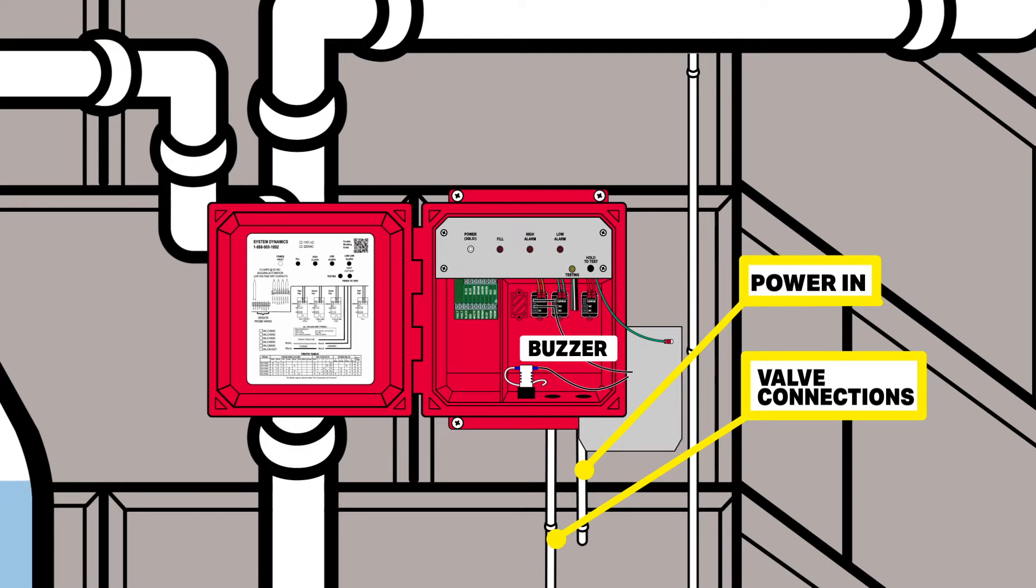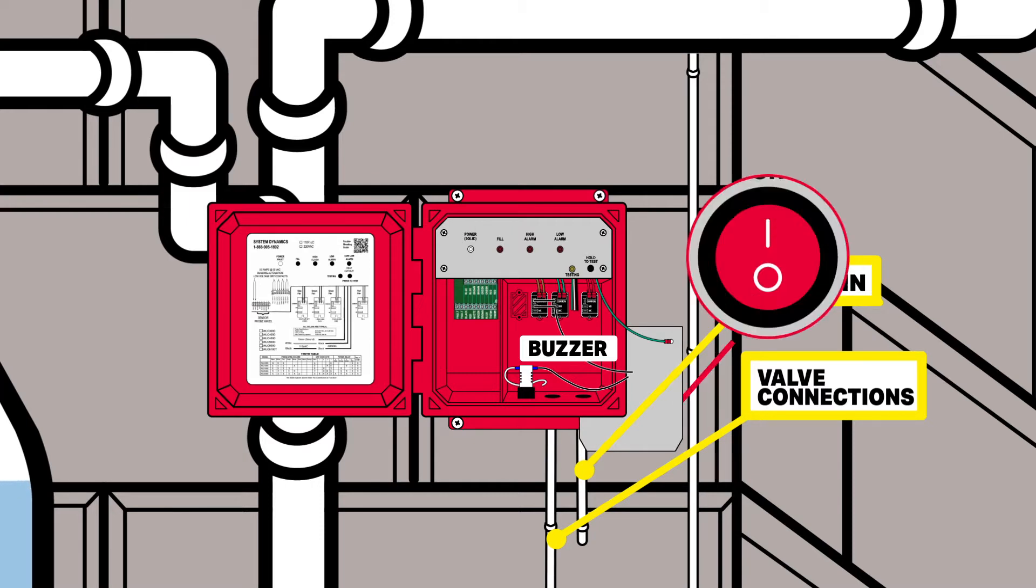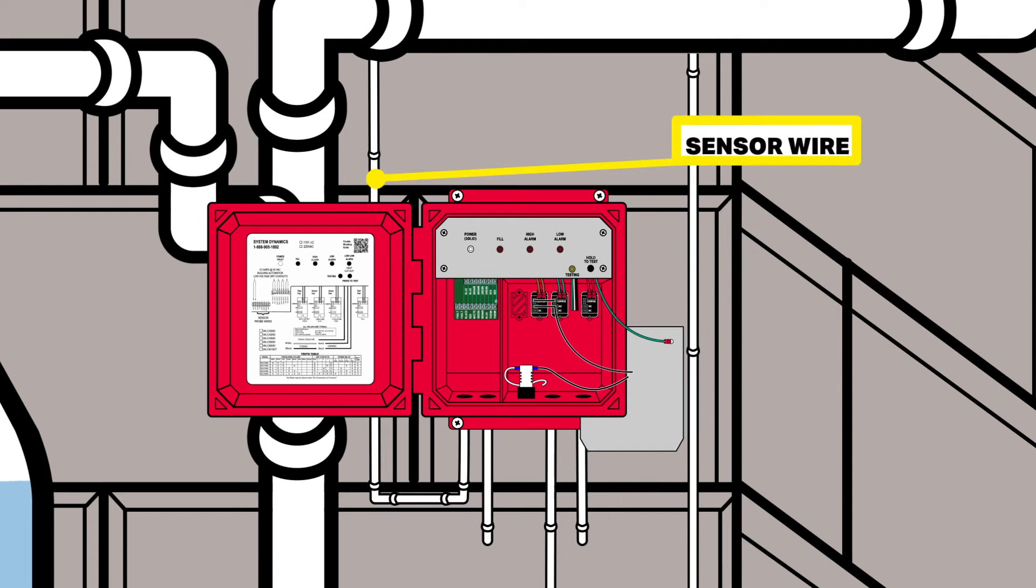There is a pre-wired audible alarm that will annunciate when the low or high alarm is triggered and a silencer switch for this alarm in the panel. The sensor wire and the remote fire panel low-voltage connections should run into the low-voltage compartment.